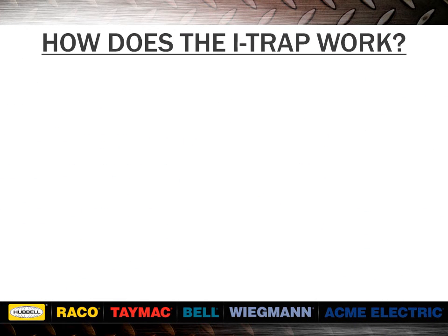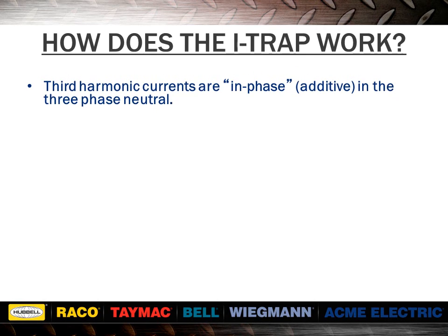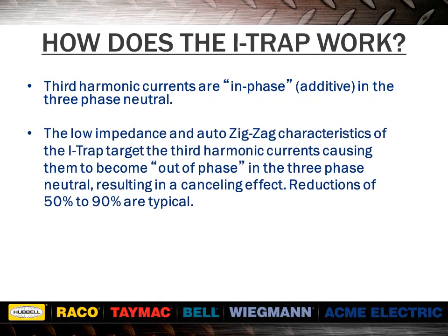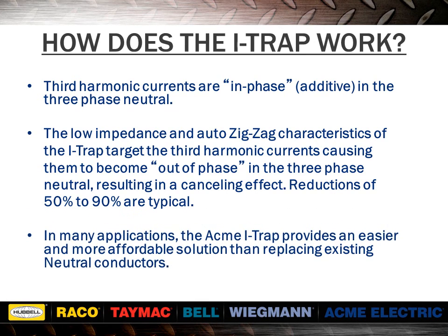How does the I-TRAP work? The third harmonic currents are in phase in the three-phase neutral. The low impedance and auto-zigzag characteristics of the I-TRAP target the third harmonic currents, causing them to become out of phase in the three-phase neutral, resulting in a canceling effect. Reductions of 50% to 90% are typical. In many applications, the ACME I-TRAP provides an easier and more affordable solution than replacing existing neutral conductors.